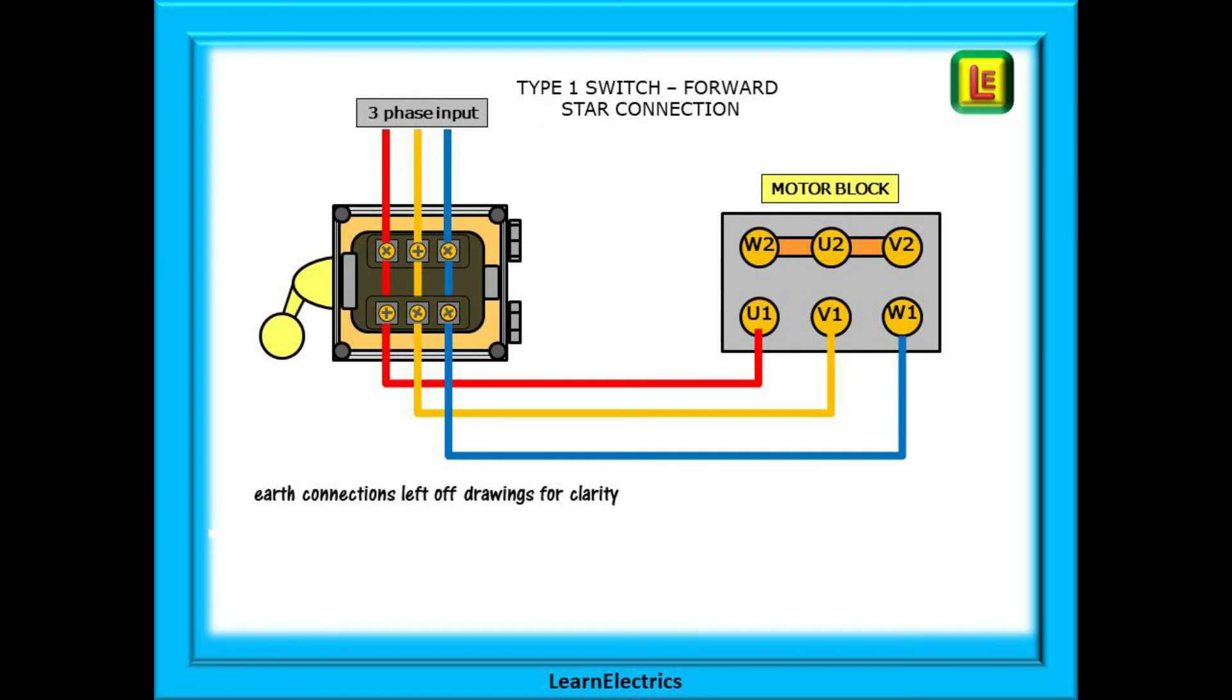In the forward position all the connections are straight through. L1 input goes to U1 on the motor. L2 to V1 and L3 to W1.